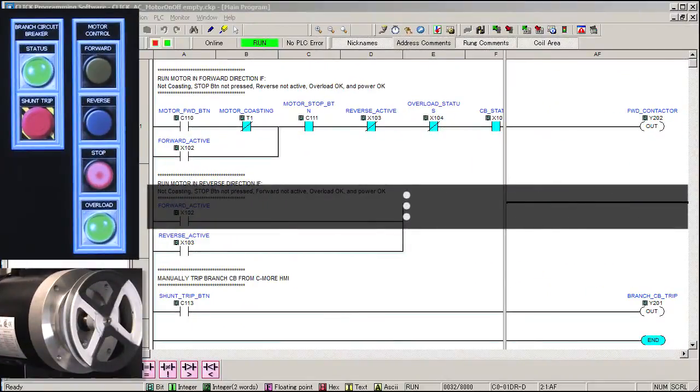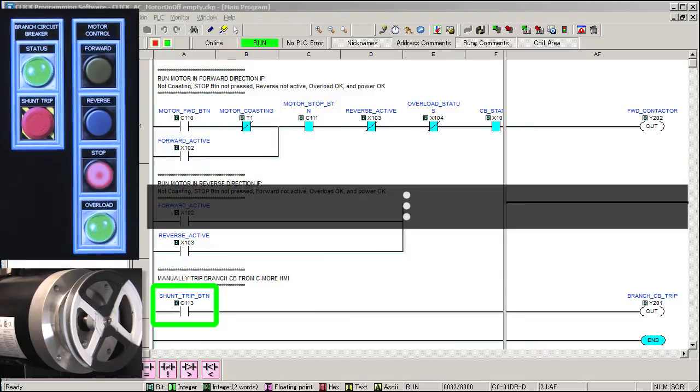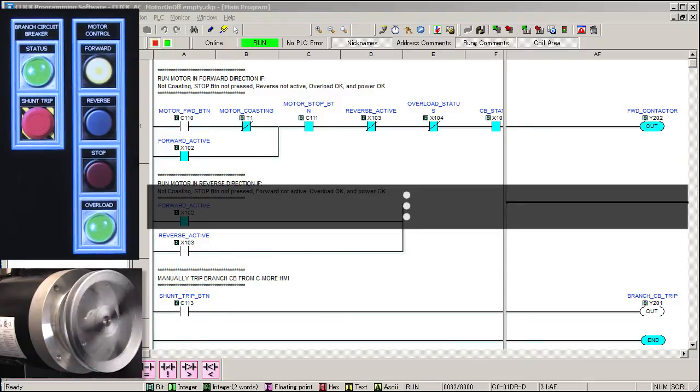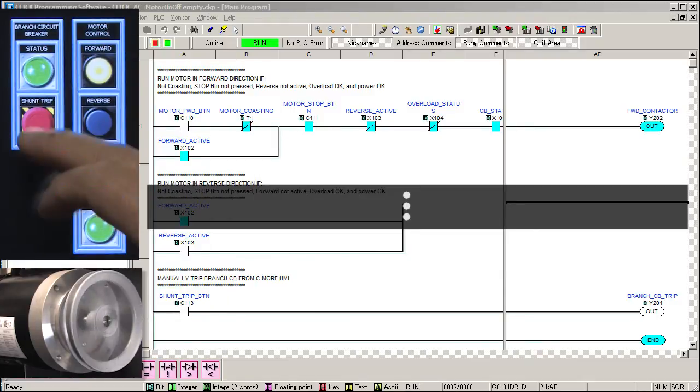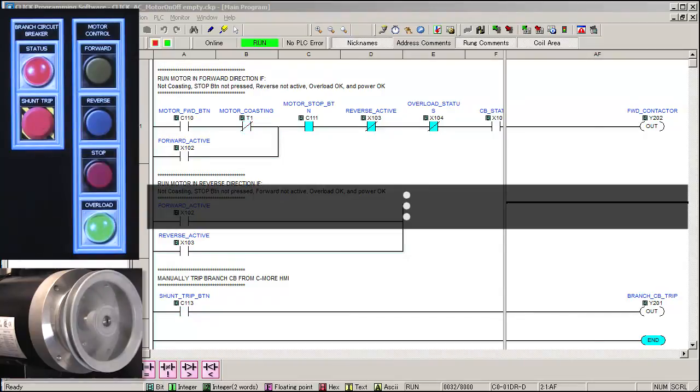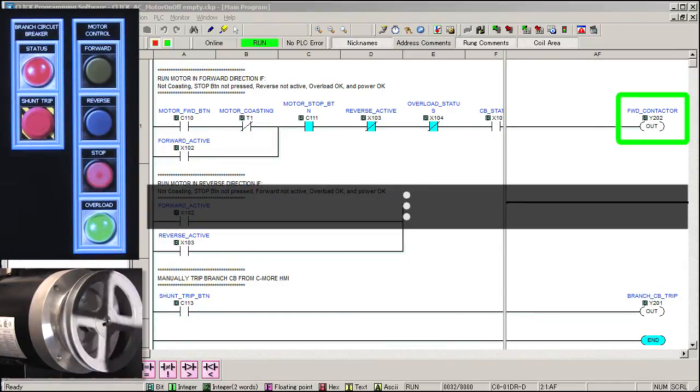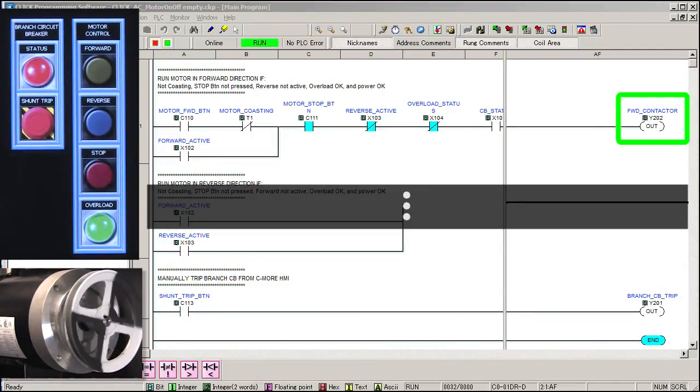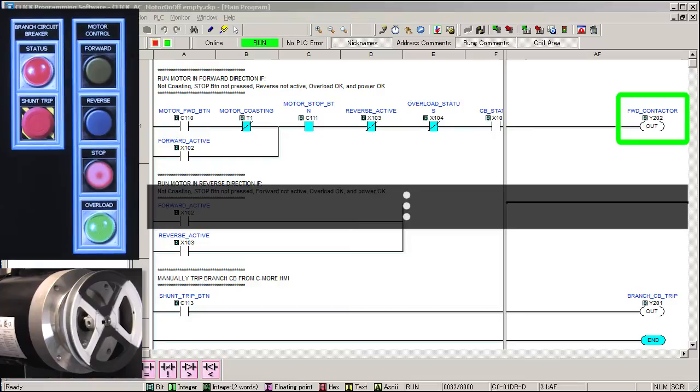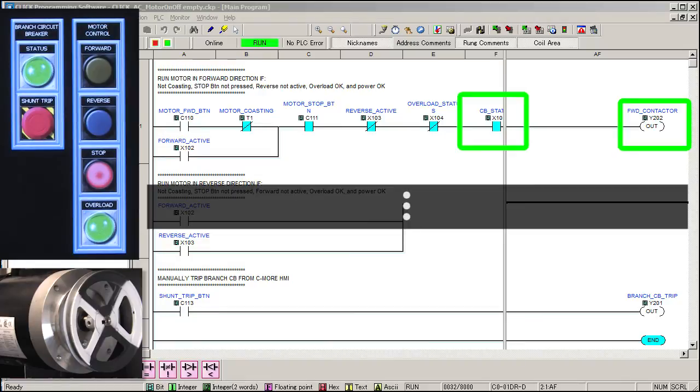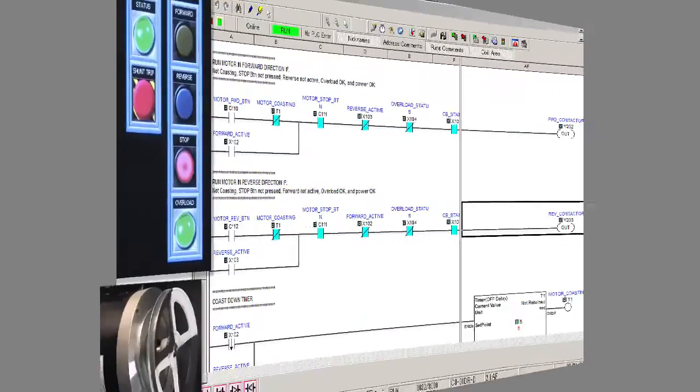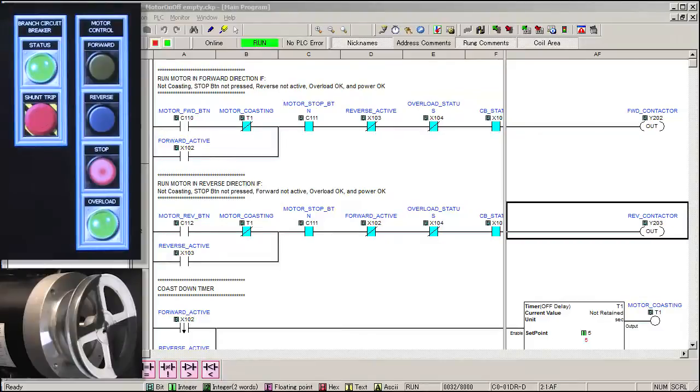Finally, let's make sure this shunt trip kills the branch circuit breaker and shuts down the motor. Start the motor in the forward direction, hit the shunt trip and no surprise here. When we kill the power to the motor, it stops. More importantly, this also breaks the sealing action of the ladder code so when the power is reapplied, the motor won't jump back to life and surprise someone. That would be an accident waiting to happen.